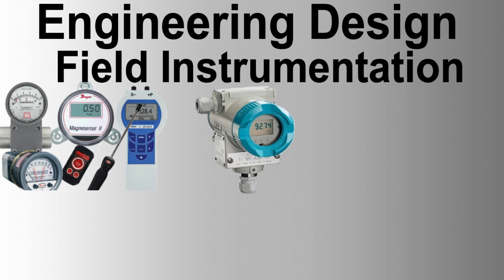Tube materials must be purchased to comply with the following standards and must be round and free of scratches on the outside diameter. The fitting supplier should confirm the maximum allowable hardness of the tube. The tube material must be stainless steel 316L with a minimum molybdenum content of 2.5%, seamless and drawn to ASTM A269 in a solution treated annealed condition, and with a maximum hardness of RB80.